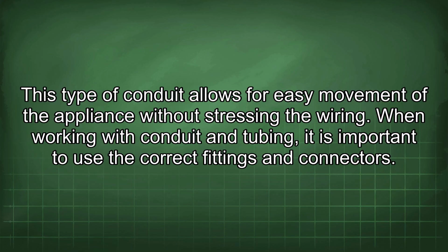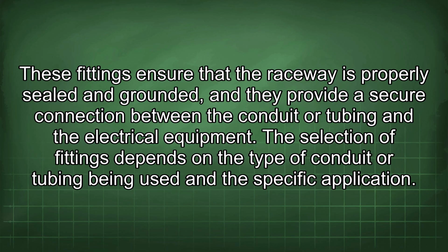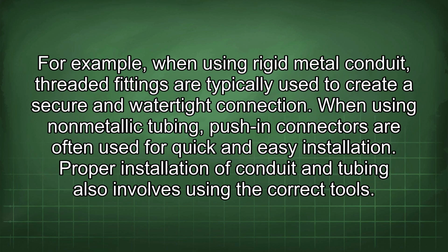When working with conduit and tubing, it is important to use the correct fittings and connectors. These fittings ensure that the raceway is properly sealed and grounded, and they provide a secure connection between the conduit or tubing and the electrical equipment. The selection of fittings depends on the type of conduit or tubing being used and the specific application. For example, when using rigid metal conduit, threaded fittings are typically used to create a secure and watertight connection. When using non-metallic tubing, push-in connectors are often used for quick and easy installation.